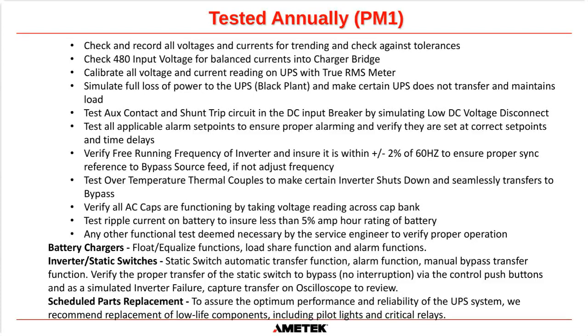For inverters and static switches, we want to check the automatic transfer function, the alarm functions, the manual bypass transfer function, and then basically we want to make sure that all of the transfers happen with no interruption. All of our FSEs have an oscilloscope with them, and they will capture those transfers, and we will be able to see the exact point of transfer and make sure that the output voltage before the transfer, during the transfer, and after the transfer is not lost. So we can do that without any issues.